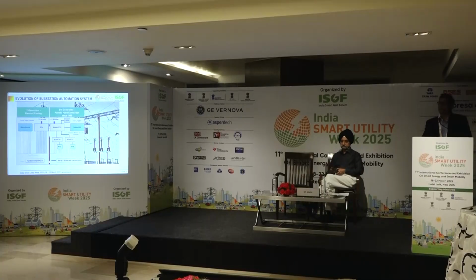Second generation, if we go forward, what we'll see is that the RTU is capable of communicating, not only collecting data from the I/O modules, but also communicating with different devices like protection devices through communication. But communication at that time was mainly point-to-point, and many of the OEMs were coming with their proprietary protocol. And in that case, the problem was that if one vendor implemented the greenfield project, the addition of any bay by another vendor was a very difficult task.